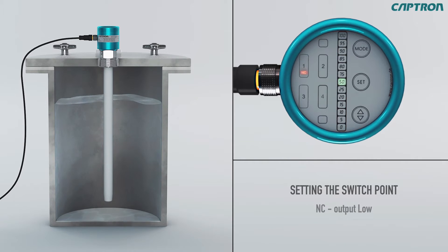With the option NC, the output is on low when the switch point is exceeded. Confirm your new setting with set. The probe then switches automatically to the setting of PNP2. Repeat the step as you perform for PNP1 and then for PNP3 and 4.